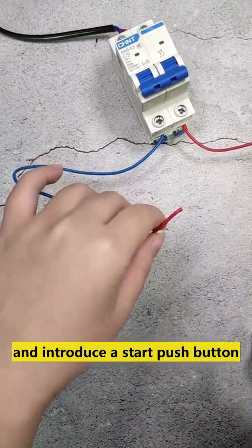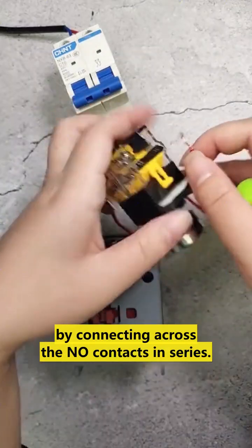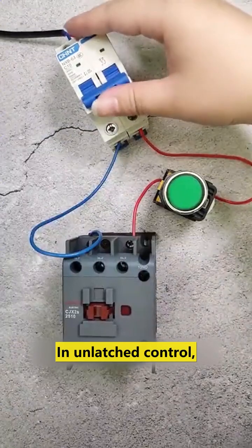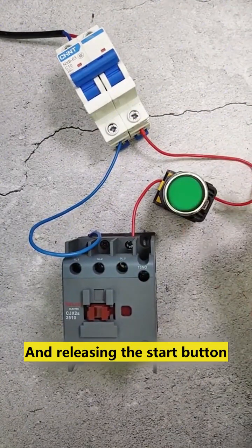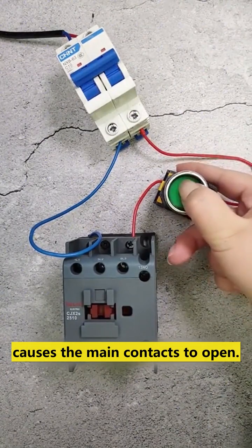Cut the live wire and introduce the start push button by connecting across the NO contact in series for unlatched control. As we press and hold the start push button, the main contact closes, and releasing the start button causes the main contact to open.